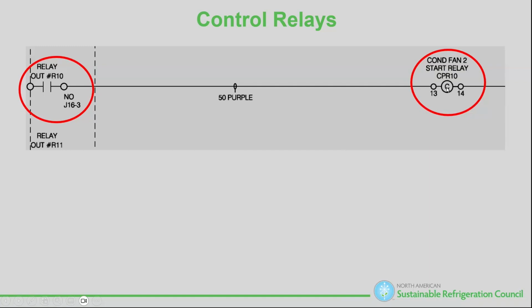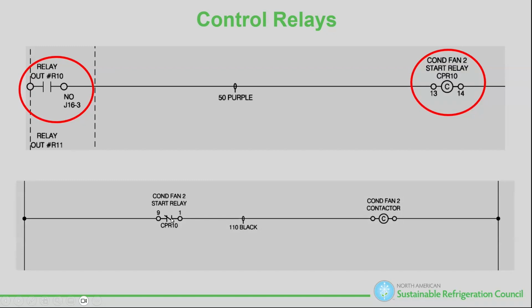When that energizes, that is going to open this set of contacts, yes? That set of contacts is going to open, actually turning off the condenser fan. This is kind of backwards because they're not using a Form C contact, they're using a Form A, so they actually had to add this relay to open this to turn that off.